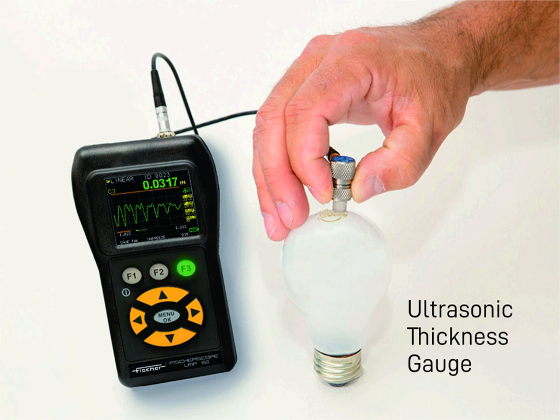Topic: Advantages and disadvantages. Ultrasonic thickness gauge advantages: non-destructive technique, does not require access to both sides of the sample, can be engineered to cope with coatings, linings, etc. Good accuracy, 0.1 mm and less, can be achieved using standard timing techniques. Can be easily deployed, does not require laboratory conditions. EMAT transducers can be used without liquid couplant.